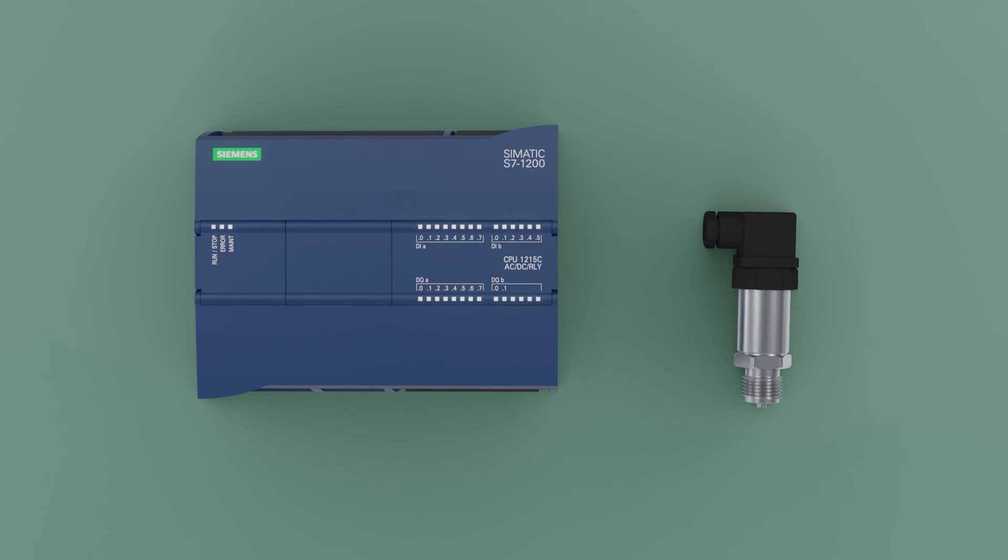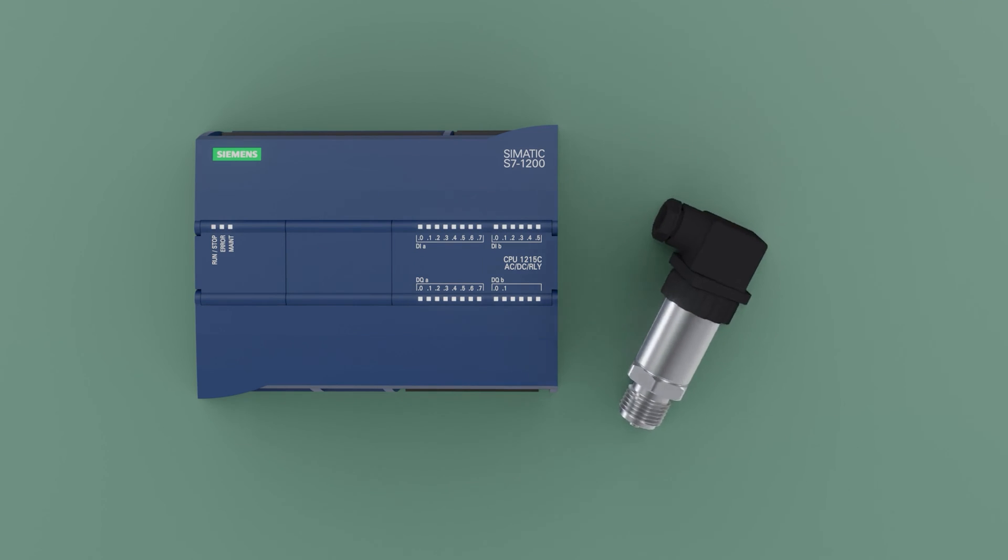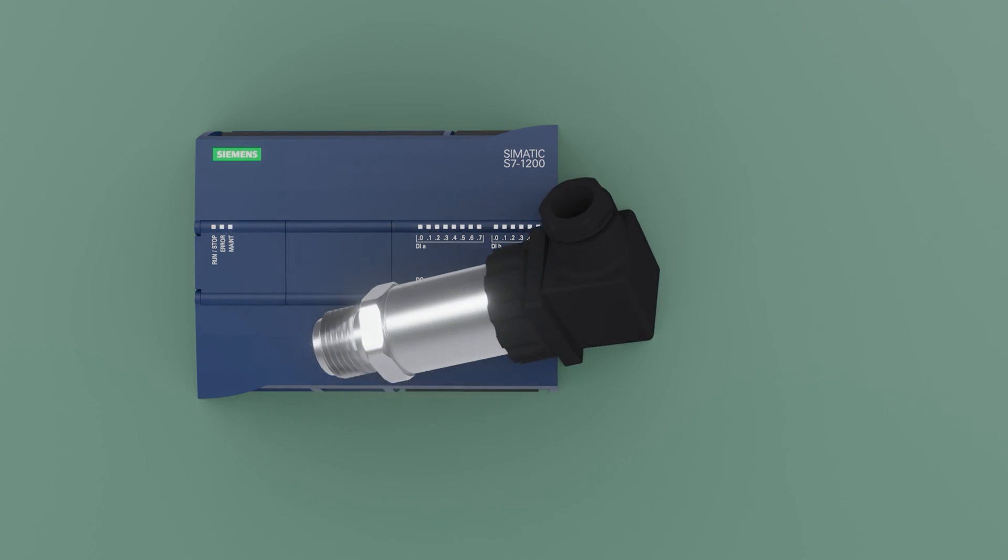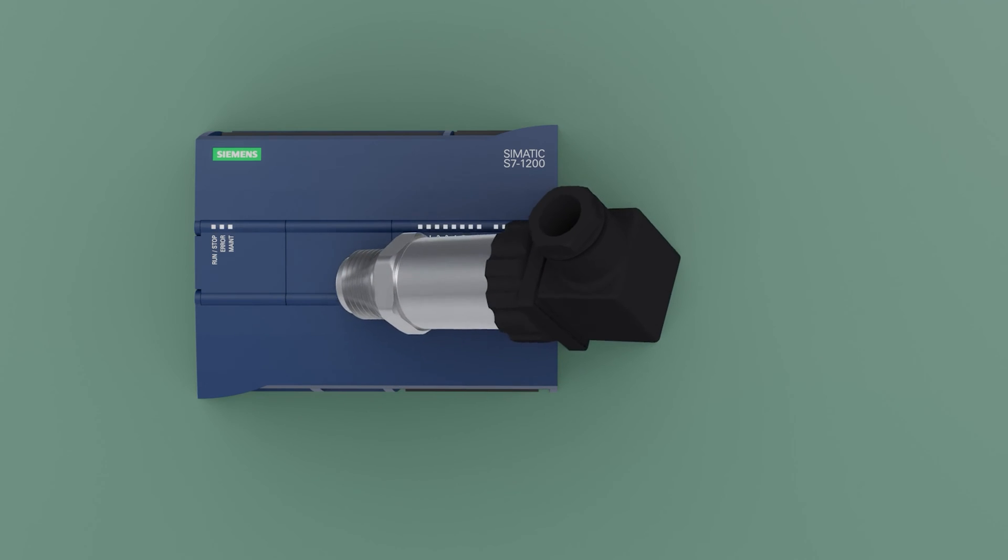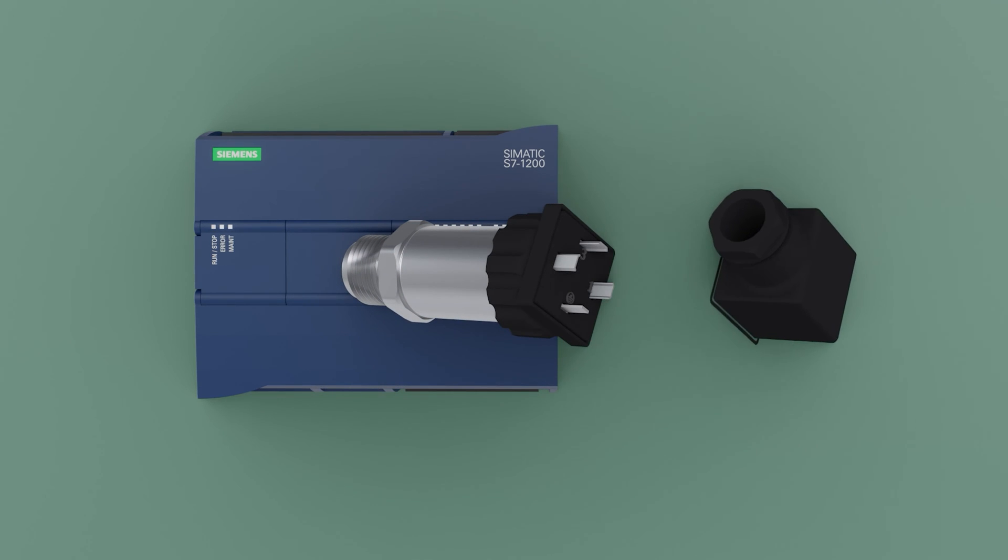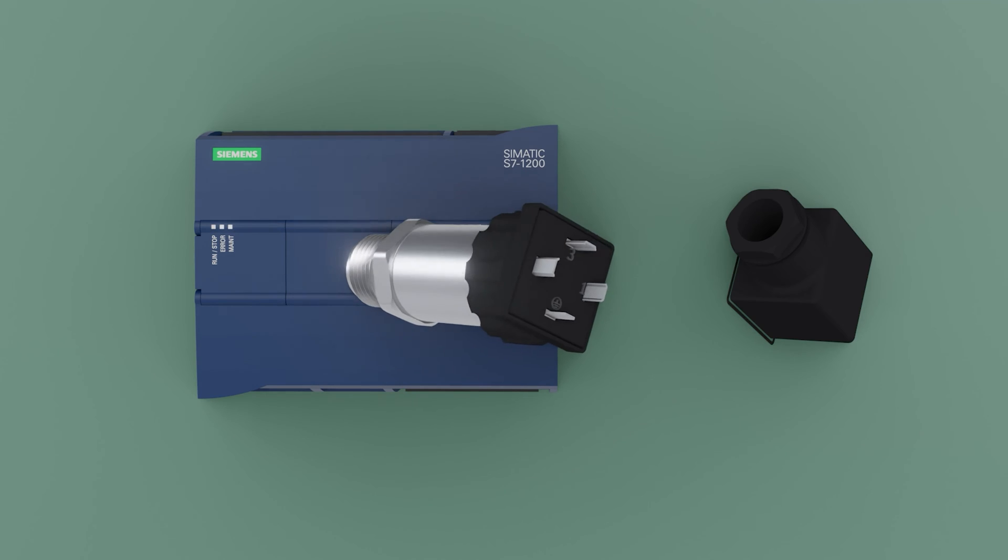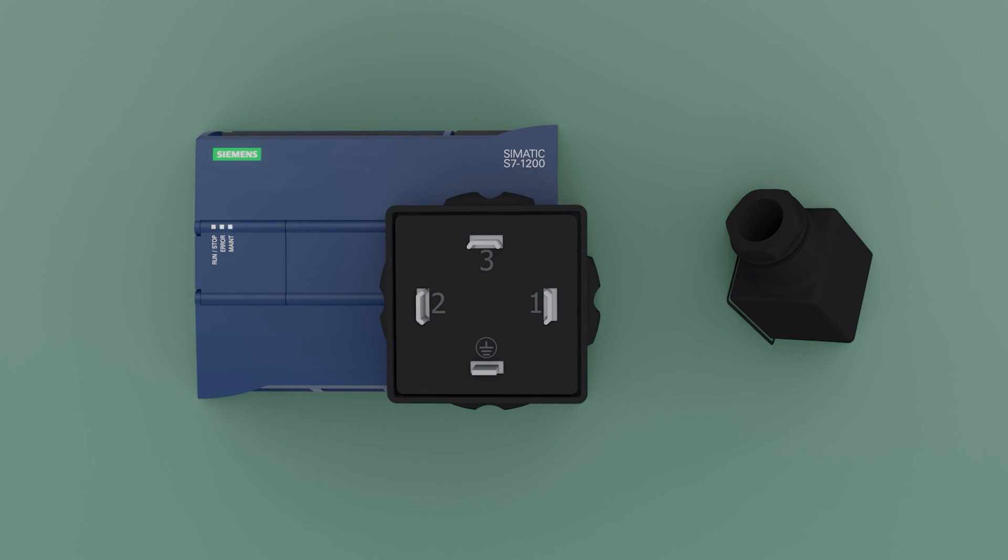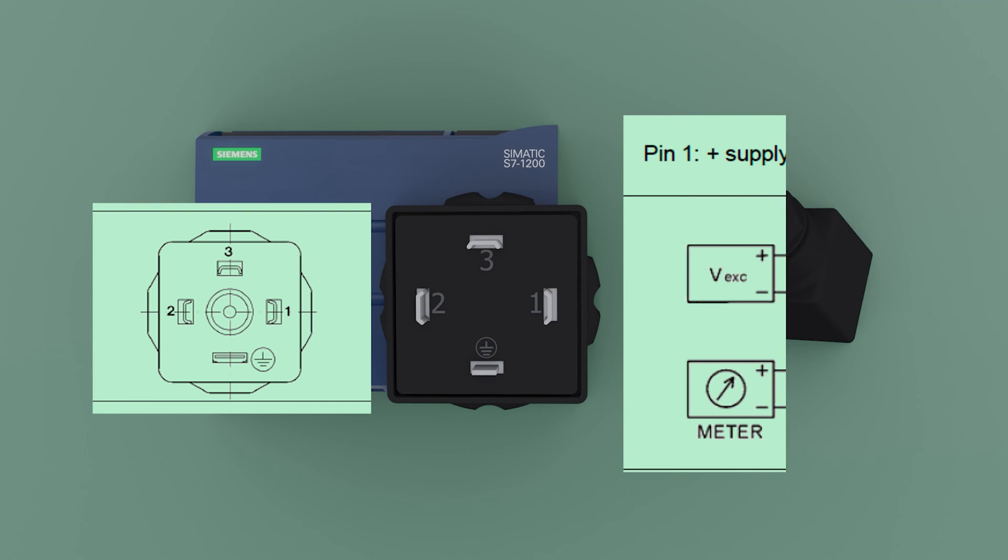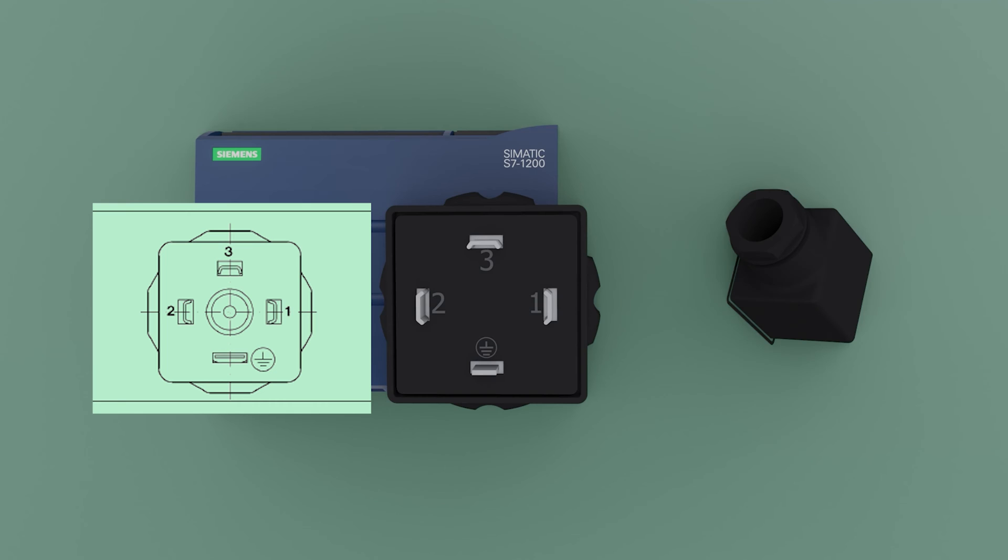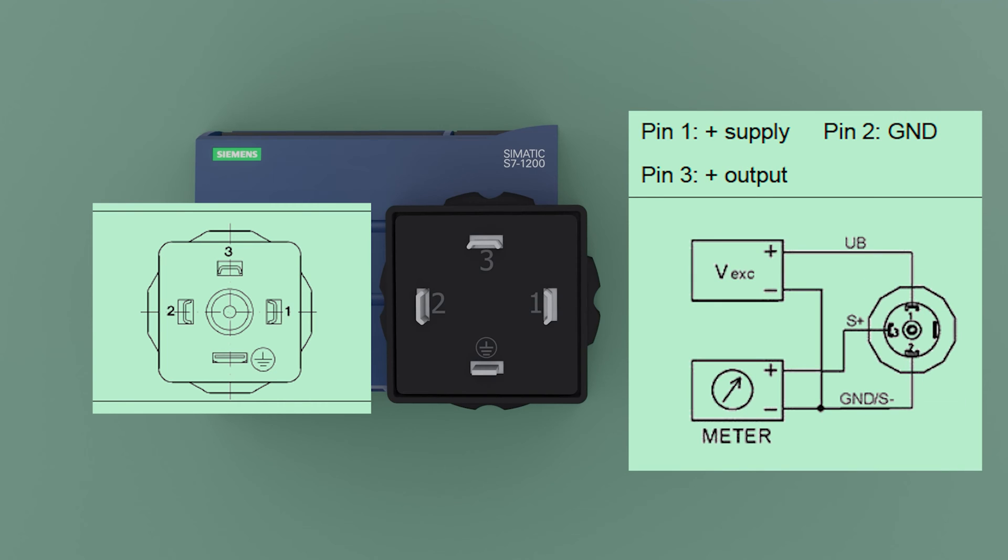This is the pressure transmitter that we will use. We have three signals. If the transmitter is current, only 1 and 2 are used. 1 is the positive, 2 is the signal. If the transmitter is a voltage transmitter, 1, 2 and 3 are used. 1 is the positive, 2 is the GND and 3 is the signal.